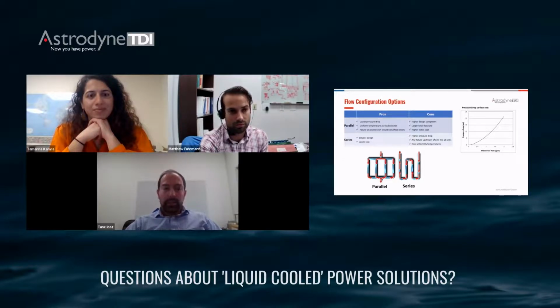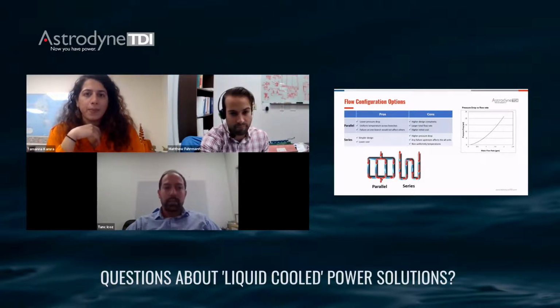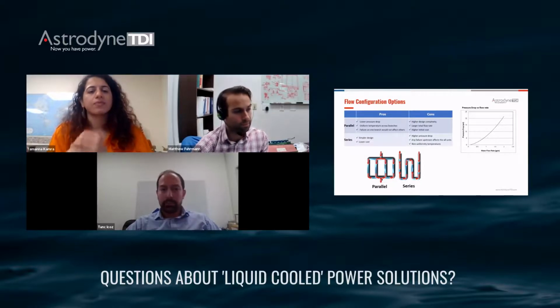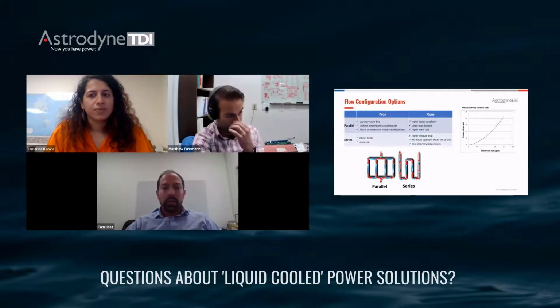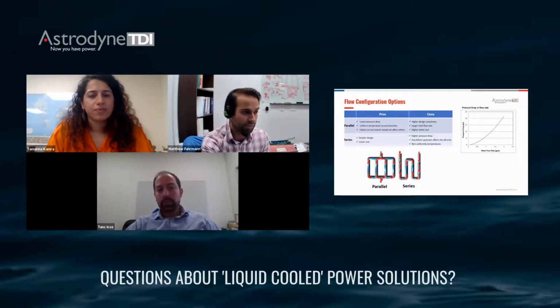In series, it's not so. You do not have the manifolds. Everything is put in series, one after the other, basically. So both configurations have pros and cons, and the system engineer will have to determine which one suits best for their specific application. I think a key piece of information is that the pressure drop increases exponentially with the flow rate. So from that standpoint, parallel arrangement has an inherent advantage over series configuration, where you split the flow, so you're not pushing as much flow through every single unit. So that ends up lowering the pressure drop. Also, the fact that flow is uniformly distributed provides a more uniform temperature distribution across different units. And another significant benefit of parallel configuration is, if something happens to one of the branches, one of the lines, the remaining lines still keep operating.